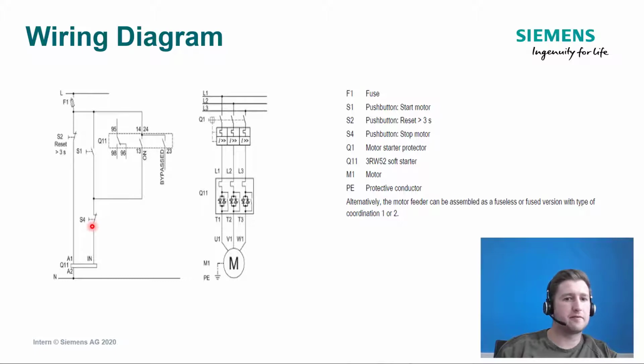If there was a fault, say for example you had an overload condition, or perhaps you had an error integrated into the soft starter, or a malfunction, what you have to do is rectify the fault, and then you have to acknowledge it here with a reset. So you have to keep the reset button pressed in for up to 3 seconds, and if you don't, you won't be able to initiate a start with S1 and the fault won't clear. with that reset command. Another way that you can reset the 3RW52 would be to hold in the test and the reset button for 3 seconds on the front of the unit.